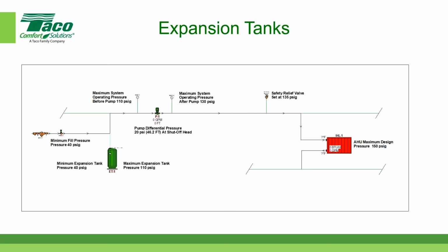And so whatever you do to one tank, if you decided to put two tanks at half the size, each tank would get pre-charged, in our case, to 40 pounds. You would pre-charge it before you connected it to the system, but you could use two tanks in lieu of one. And that typically happens if you have a very, very large system, and it's not practical to put in a single size tank. You want to put in multiple tanks.